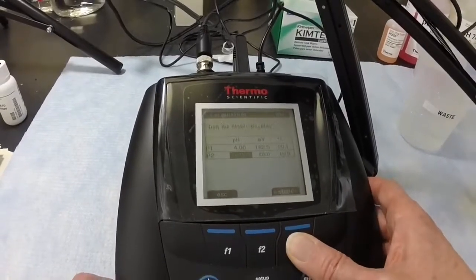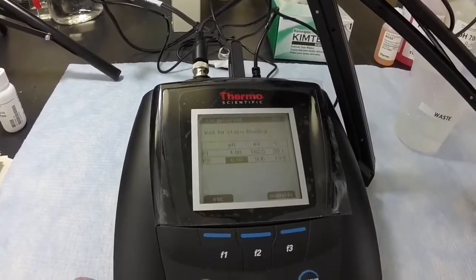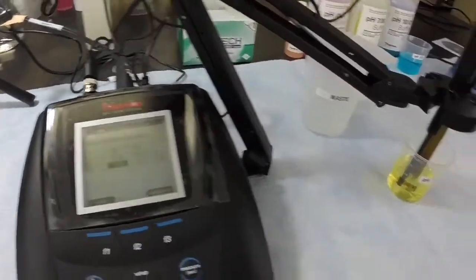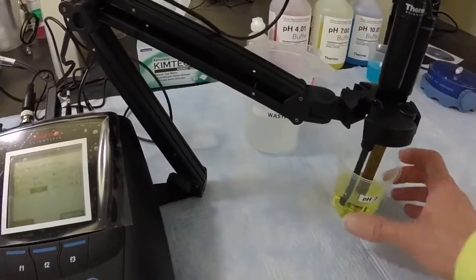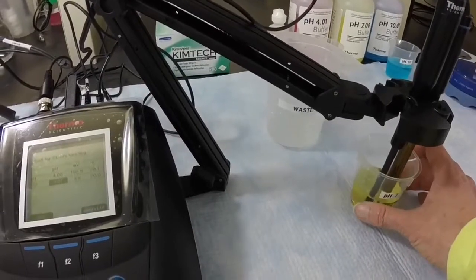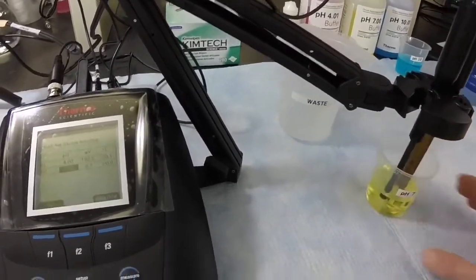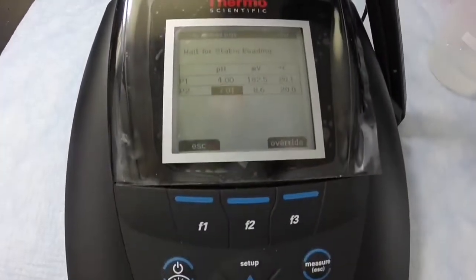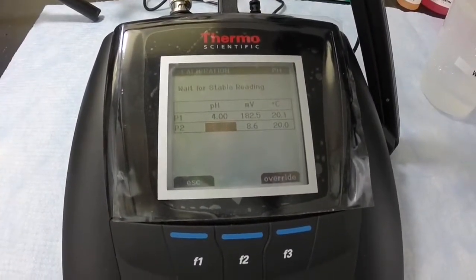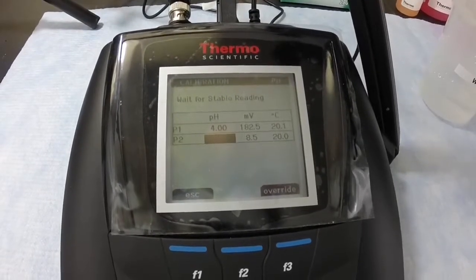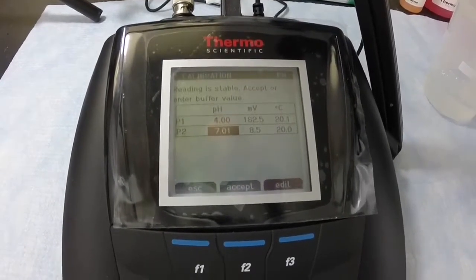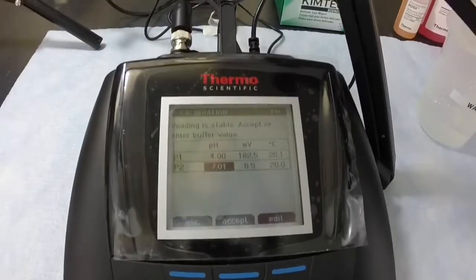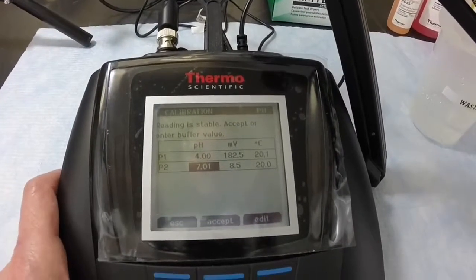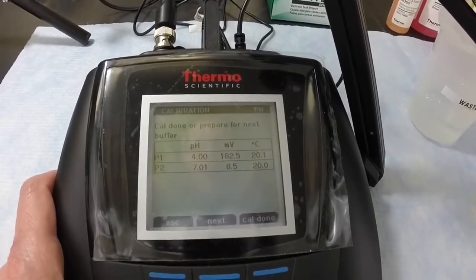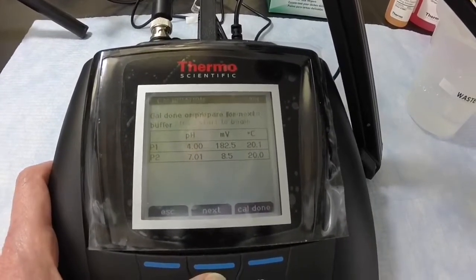The pH will display and blink while waiting for the reading to stabilize. When the reading is stable, it will stop flashing and lock on the correct pH value for that buffer at the temperature measured. We choose the option to accept the second calibration point. Since we're doing a 3-point calibration, we press Next for the last calibration point.